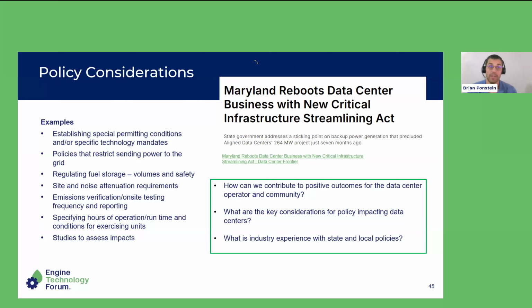Typically, for most of the data center applications, the fuel is stored beneath the unit, whether you call that a belly tank or a day tank - they can take on several different terms. Typically that's sized to operate the unit for somewhere between, I'd call it 8 hours - usually about a day worth of activity, whether that's 8 hours or 24 hours. Sometimes it's more - it could be dictated by code to be up to, I think it's 96 hours in some cases. But for most of these data center type applications, this is more around a day's use of fuel on site, which for these large units that are consuming a lot of fuel, this could be several thousands of gallons of diesel fuel per unit.